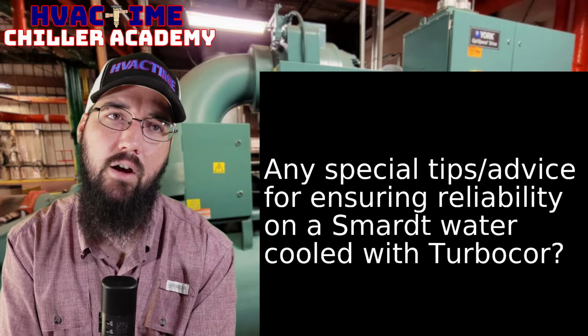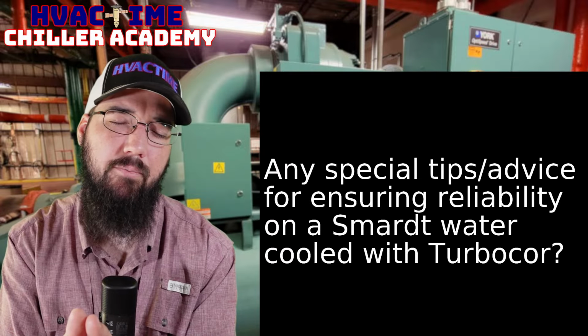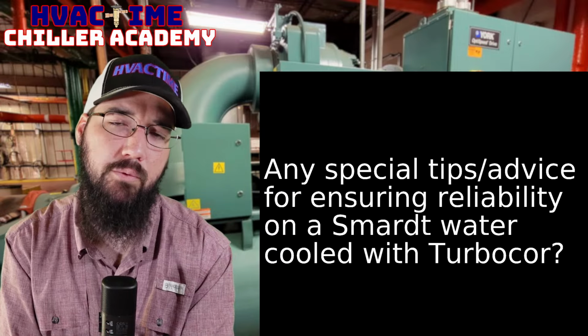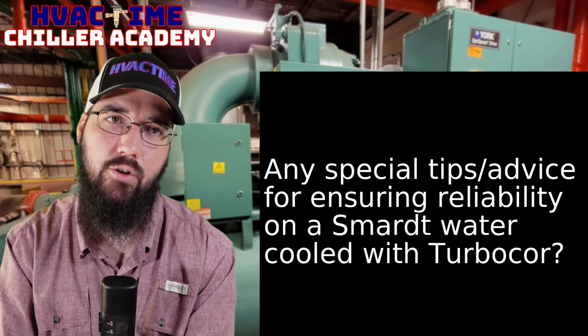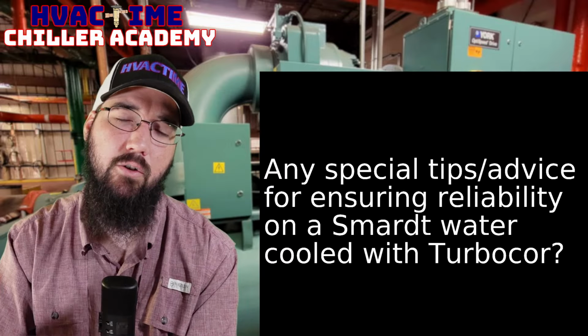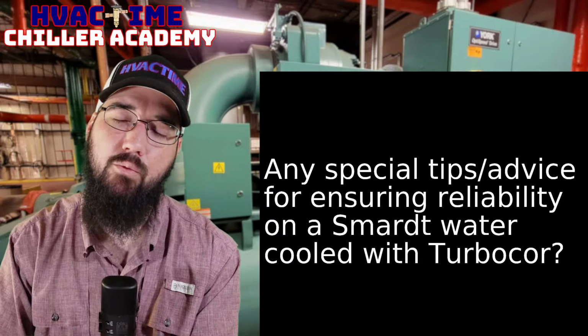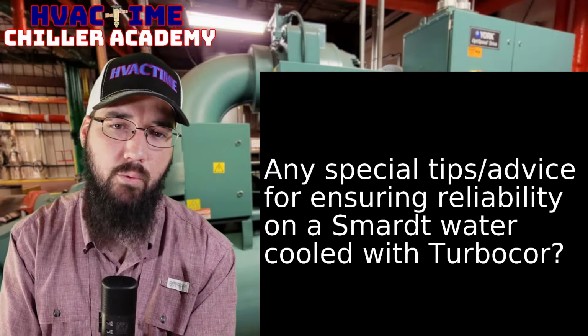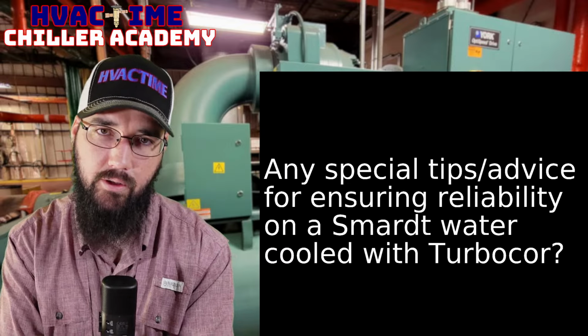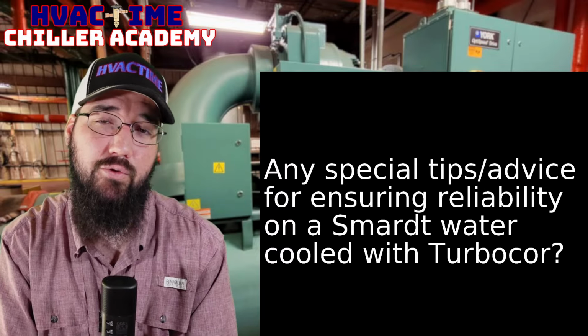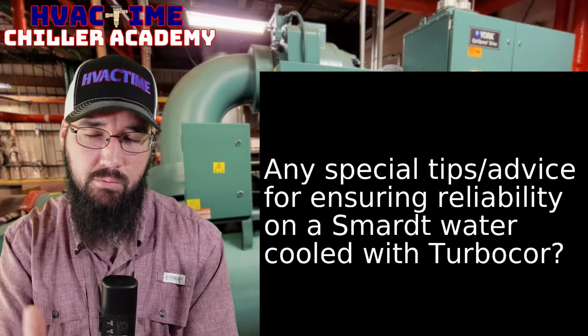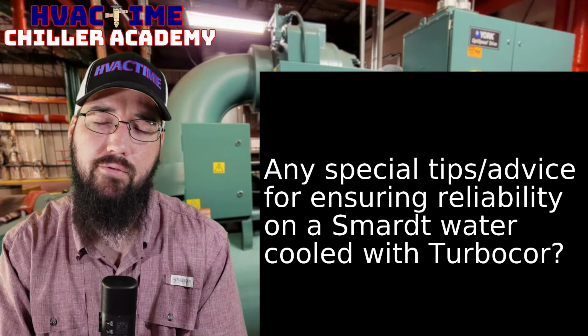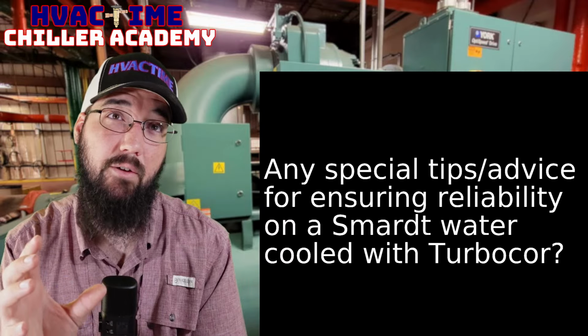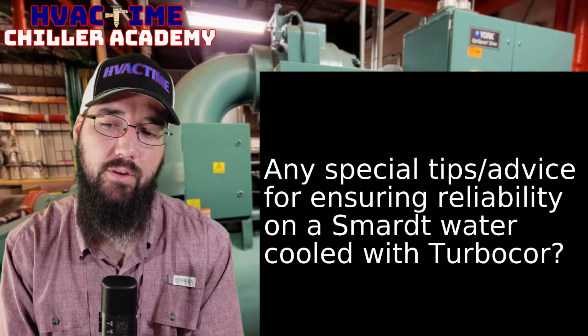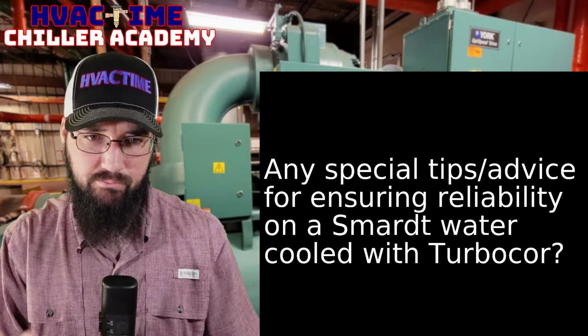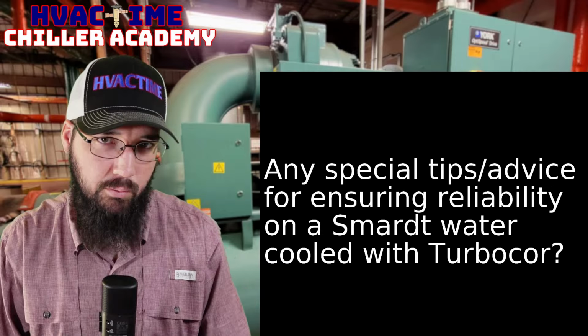So it worked very similarly to how the Carrier 30HX and GX external oil pumps worked, where they came on right as the compressor was starting up. Then as we established differential pressure across the machine or across the circuit, it would shut the external pump down and then run on the bypass circuit from there for oil flow, right? So I've seen it done both ways on those. If that's not something they already have, that liquid cooling pump is something to consider. They're not that hard to put in, and most control systems have it. I know Smardt has built-in control logic for that pump, or an output for it, and I'm pretty confident they can, as an option, ship those with it. So if that's not there, that's something kind of specific or special, but again, that's a Turbocor thing.